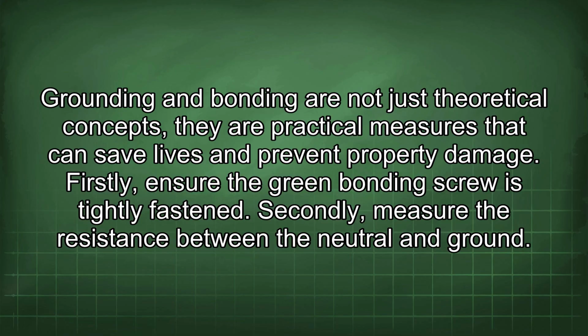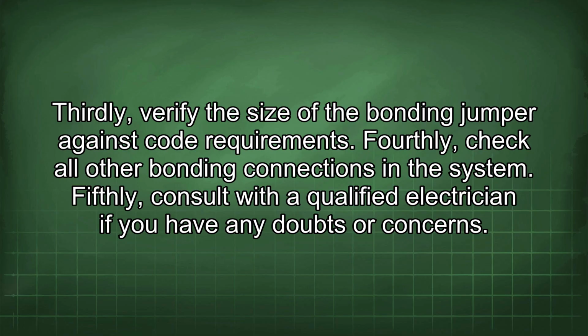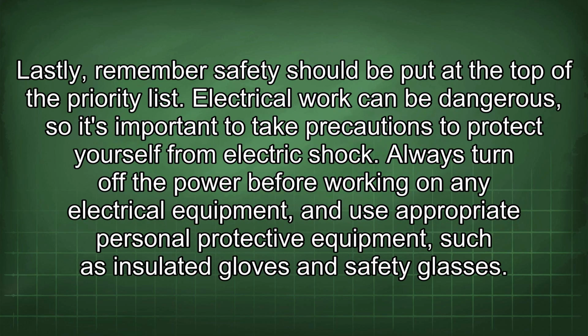Firstly, ensure the green bonding screw is tightly fastened. Secondly, measure the resistance between the neutral and ground. Thirdly, verify the size of the bonding jumper against code requirements. Fourthly, check all other bonding connections in the system. Fifthly, consult with a qualified electrician if you have any doubts or concerns. Lastly, remember safety should be put at the top of the priority list. Electrical work can be dangerous, so it's important to take precautions to protect yourself from electric shock. Always turn off the power before working on any electrical equipment, and use appropriate personal protective equipment such as insulated gloves and safety glasses.